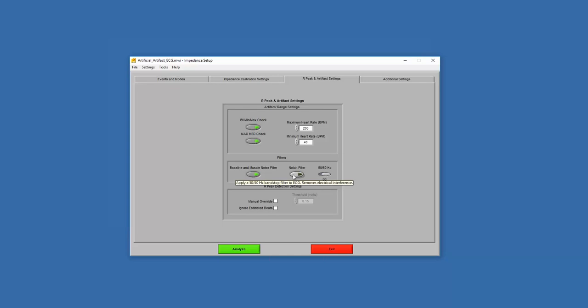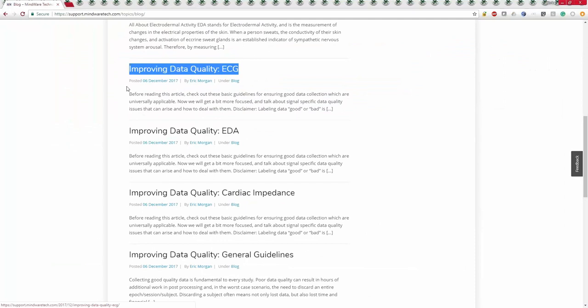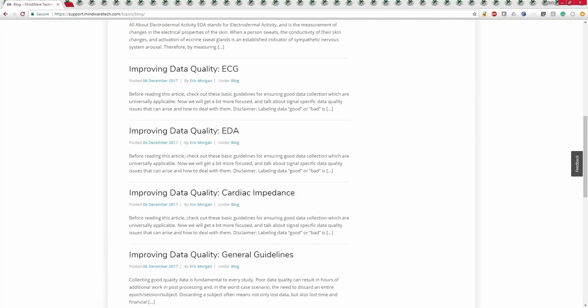The notch filter: for those of you who've collected data before, if someone's touching a power cord or near a transformer, you can get electrical interference that makes everything look fuzzy. By turning on this notch filter, that'll get rid of either 60 Hz in North America or 50 Hz for European data. We have articles on the support site — 'Improving Data Quality: ECG' — that show you examples of what 60 Hz interference looks like on ECG and on impedance, so you can confirm whether you have that issue.